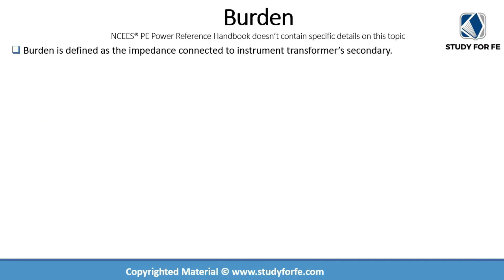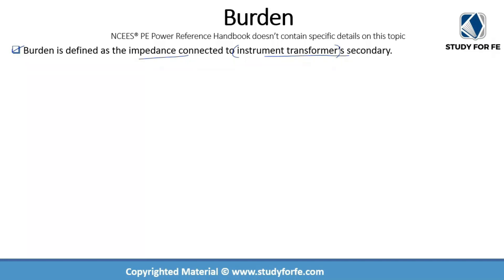So what is burden? Burden of an instrument transformer is defined as the impedance which is connected to the instrument transformer's secondary. I'm using the general term instrument transformer because burden is applicable to both current transformers as well as voltage transformers. Burden includes the transformer's own secondary impedance and that of the devices and connecting leads — everything connected on the transformer's secondary. IEEE expresses burden in terms of ohms, whereas IEC expresses burden in volt-amperes.